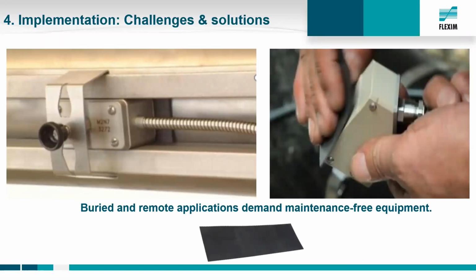Another part of the installation itself is the coupling. Coupling means the connection between the transducer and the pipe. It is very important because we want to ensure a proper and stable injection of the ultrasound signal into the pipe and the fluid. So coupling the transducer to the pipe with a permanent coupling pad is recommended from our side, from our view and experience, because there are different coupling methods like paste, gel, or grease, and dry coupling like these pads.